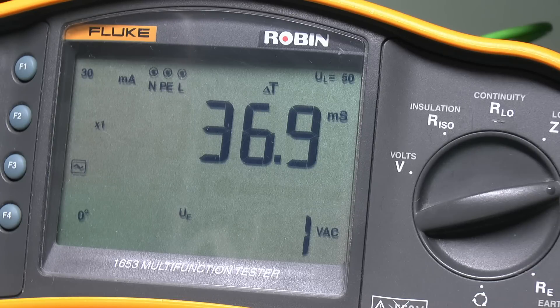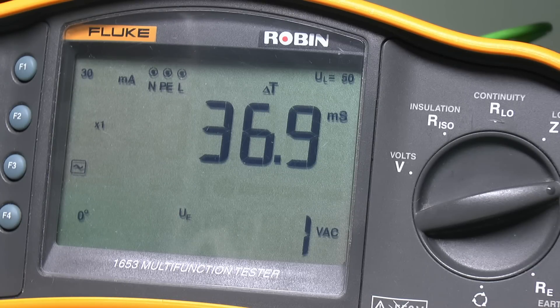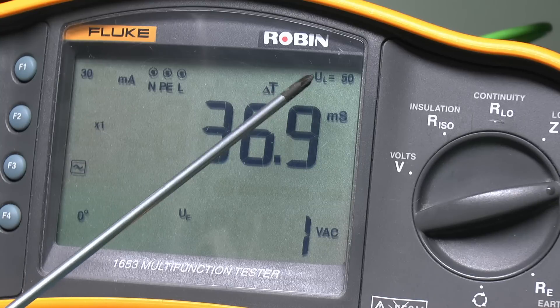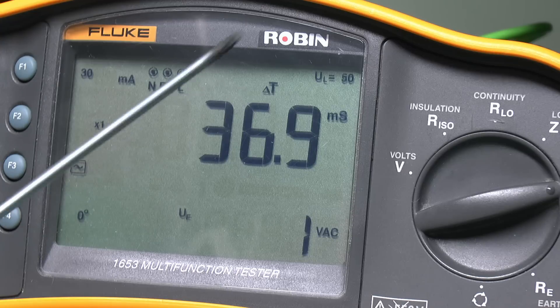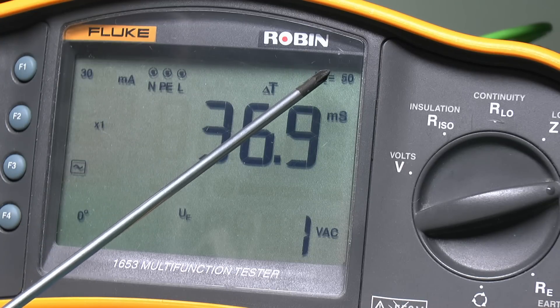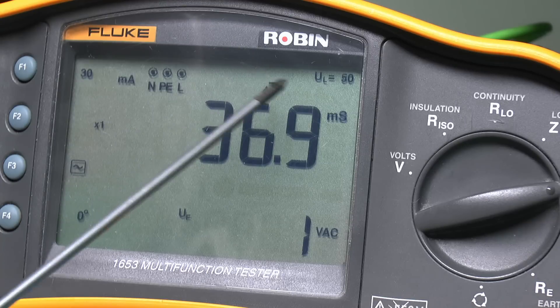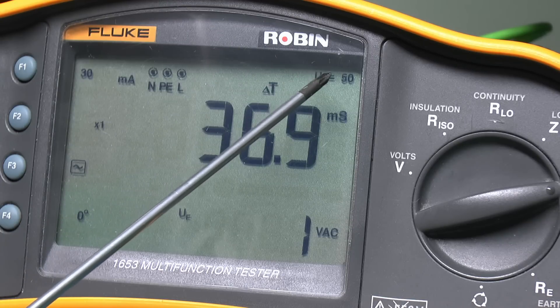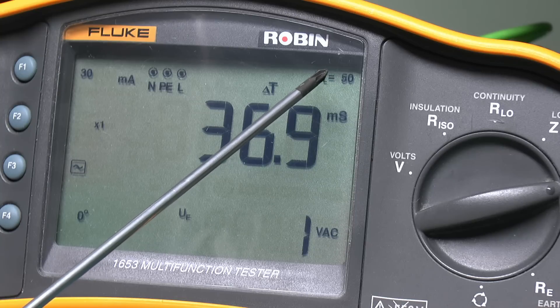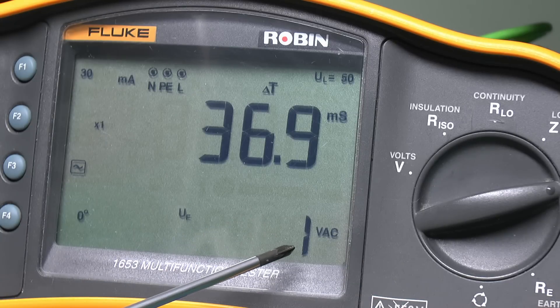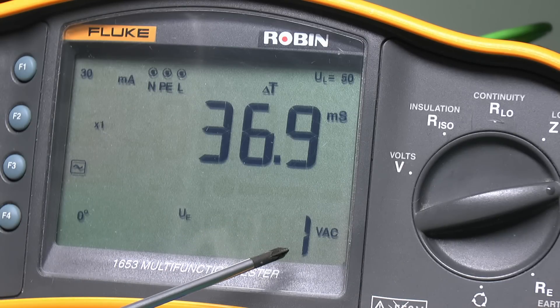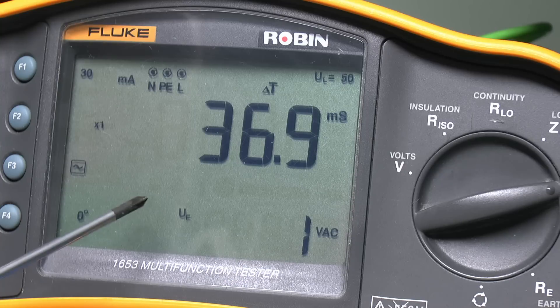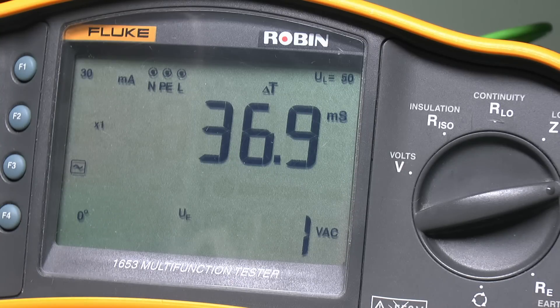And to finish with just a couple of other points to note on the display here, and we've got at the top here a UL which is essentially the maximum voltage allowed to appear on the earth during the test, which in this case is 50 volts. And again that's why I need those three leads connected because the device will actually check beforehand and see if that voltage would be exceeded, and it won't actually do the test if that was the case. And then down here I've actually got the voltage which will appear there, which in this case is just one volt, so pretty much nothing at all. And again that's just showing the UF here, or the fault voltage.